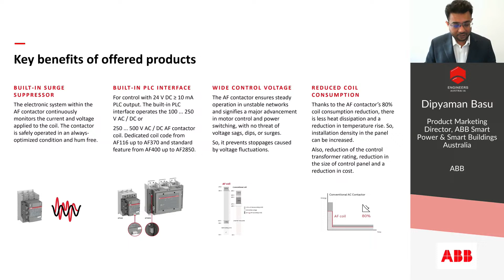With the built-in PLC interface, the AF contactor range also offers very low power for PLC outputs. When it comes to steady operation, AF contactors have a wide control voltage range, and this capability helps in maintaining continuity of control circuits, allowing different voltages to be used, which can prevent stoppages caused by voltage fluctuations. With lower energy consumption of the AF contactors, we can also effectively reduce heat dissipation and temperature rise, which in turn can allow higher installation density in control panels. And of course, that leads to cost savings.